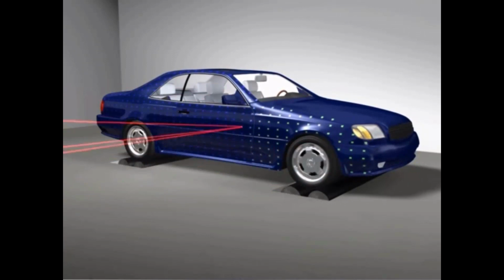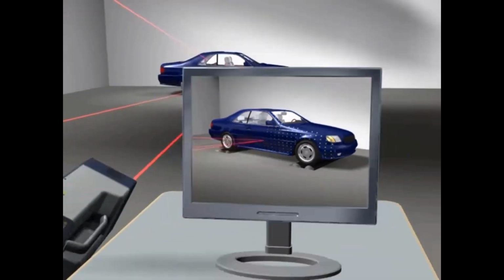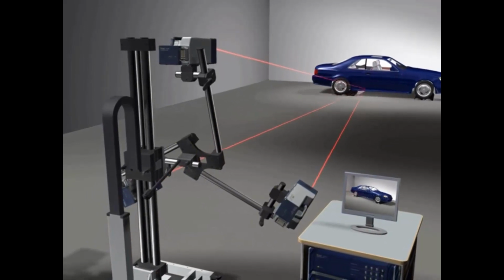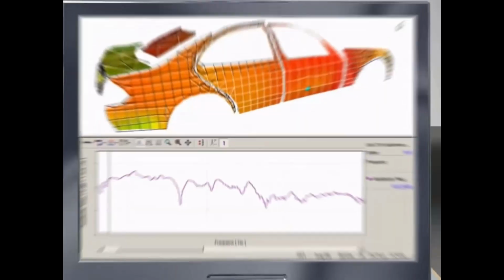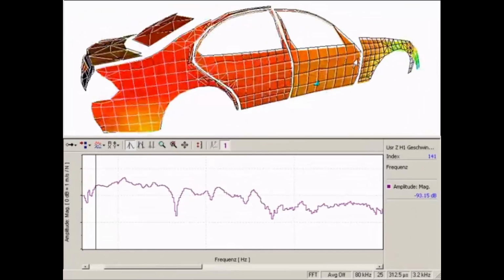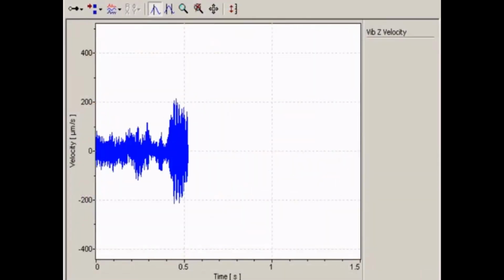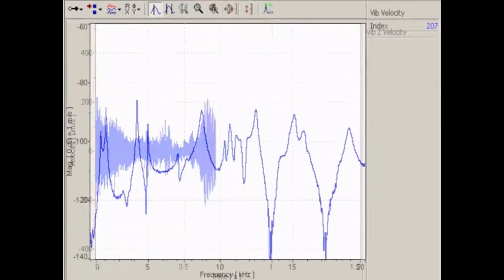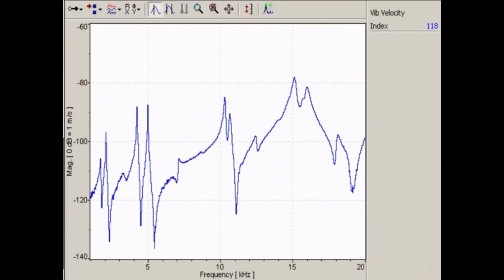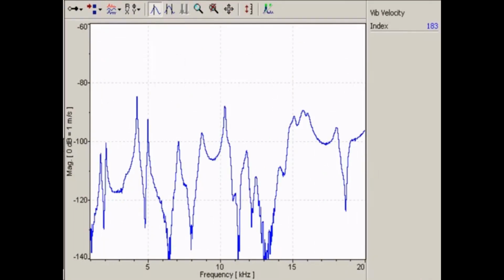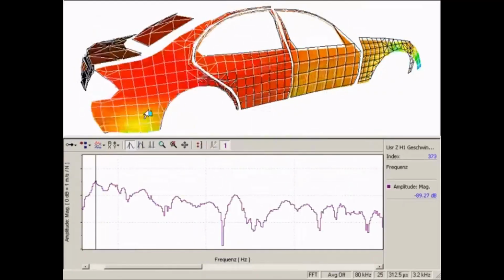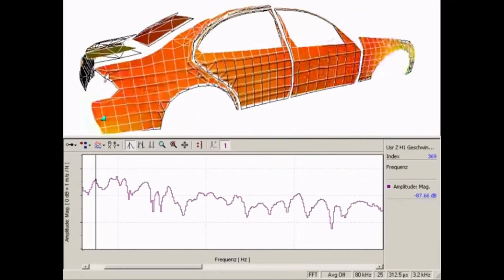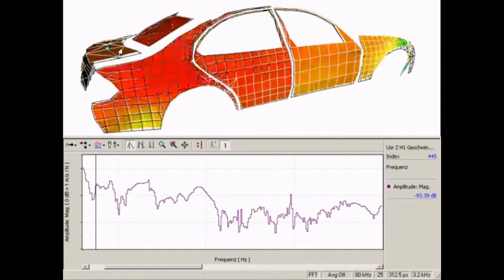By using scanning mirrors, the light is sequentially placed on a grid of points, measuring the motion of a complete surface. 3 measurement heads sample each grid point in 3 separate directions, uniquely determining the vector motion at that point. Vibrometers deliver meaningful results. Real-time data help to visualize the temporal signature, and frequency spectra display the characteristic resonances. For full field measurements, spatial deflection shapes are visualized as an animated pseudo-color representation, or as a dynamic 3D graphic for a better understanding of the overall system response.